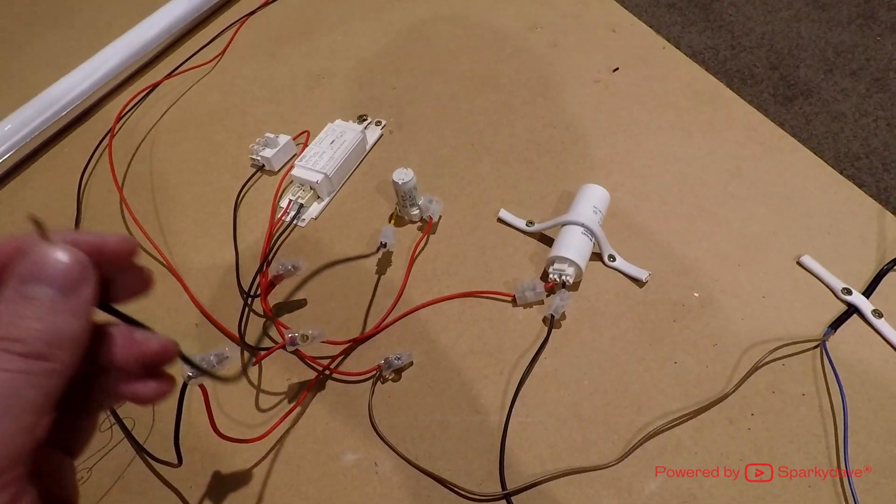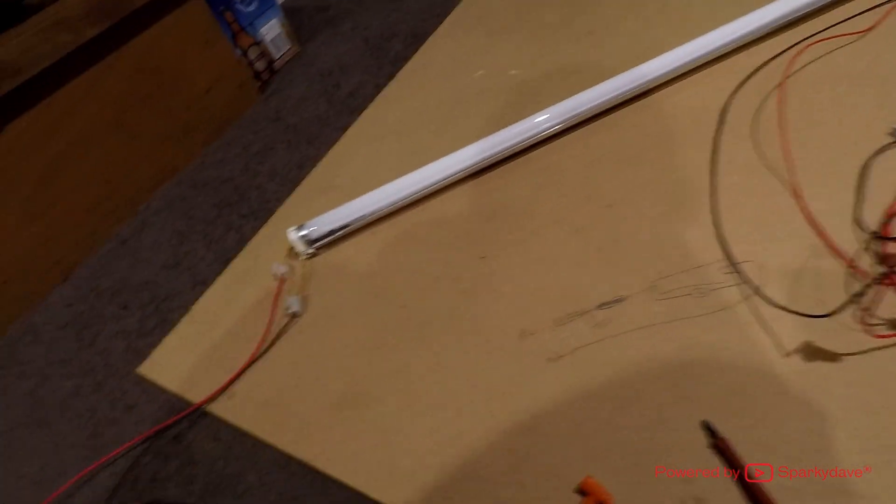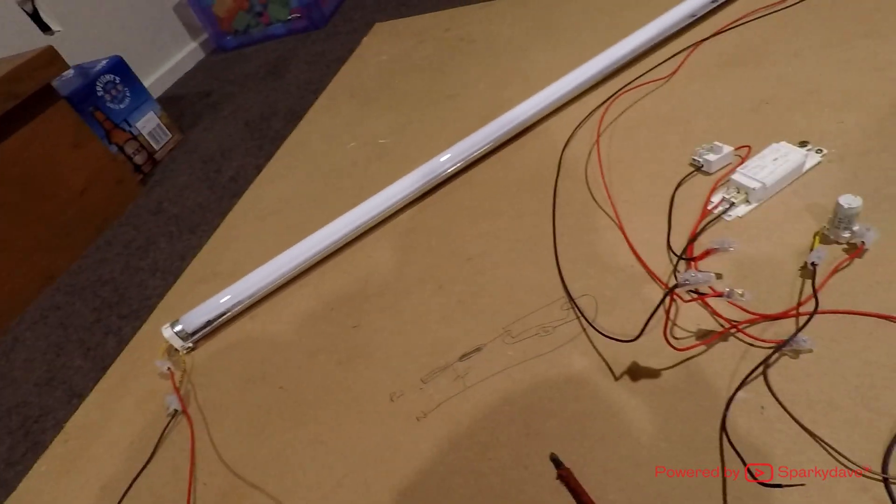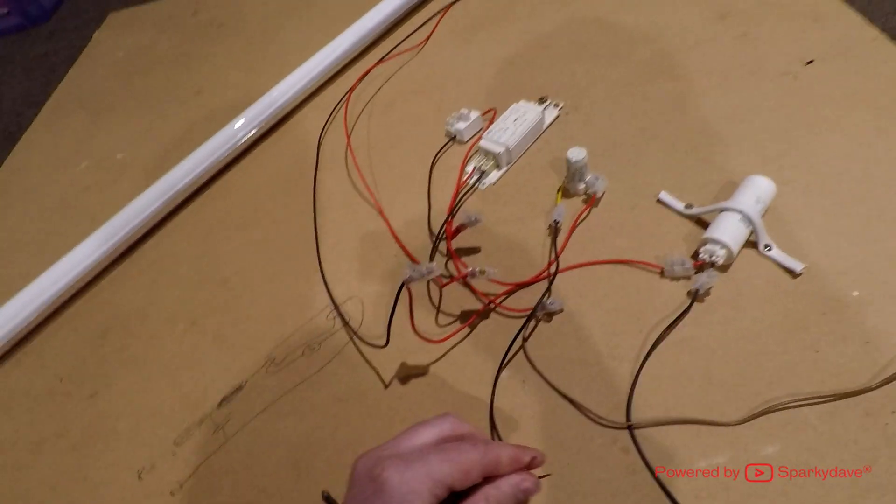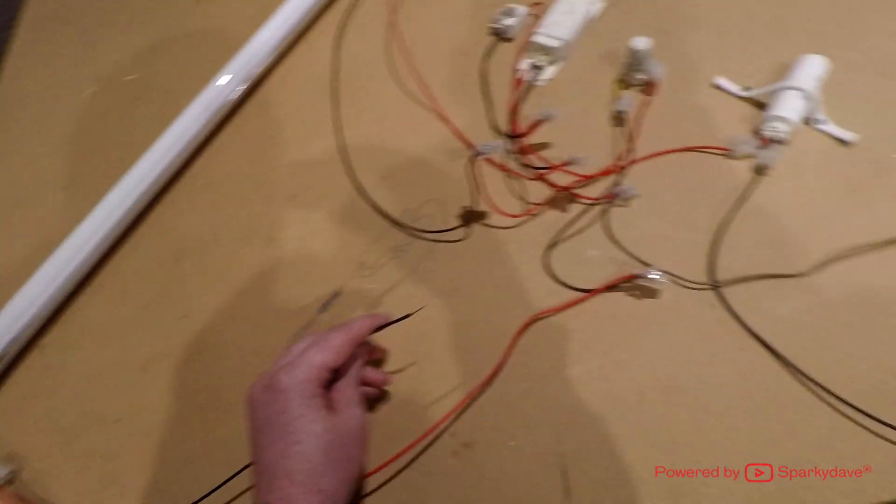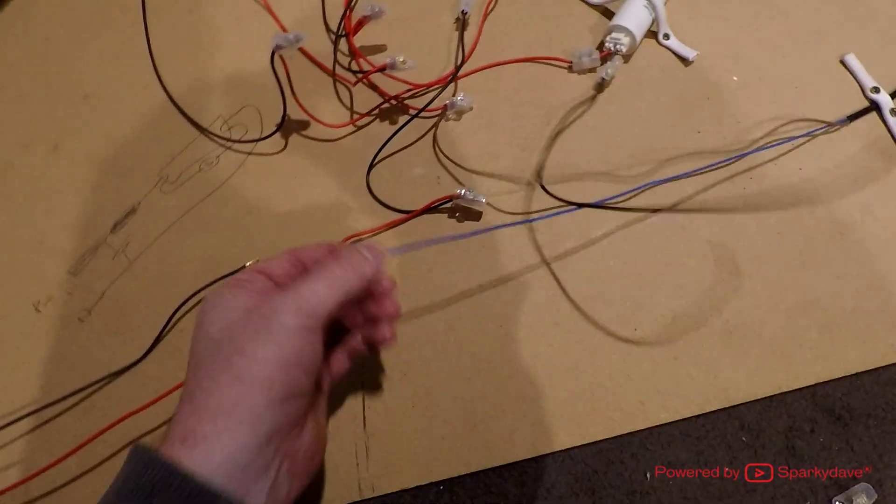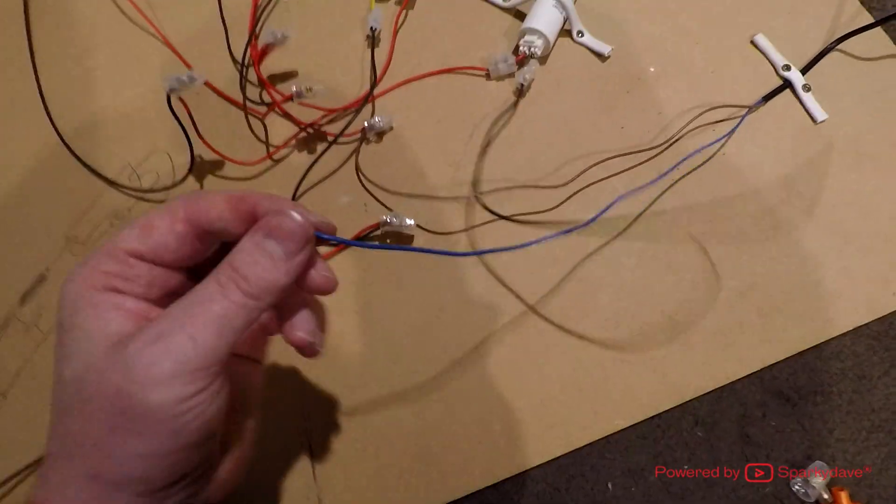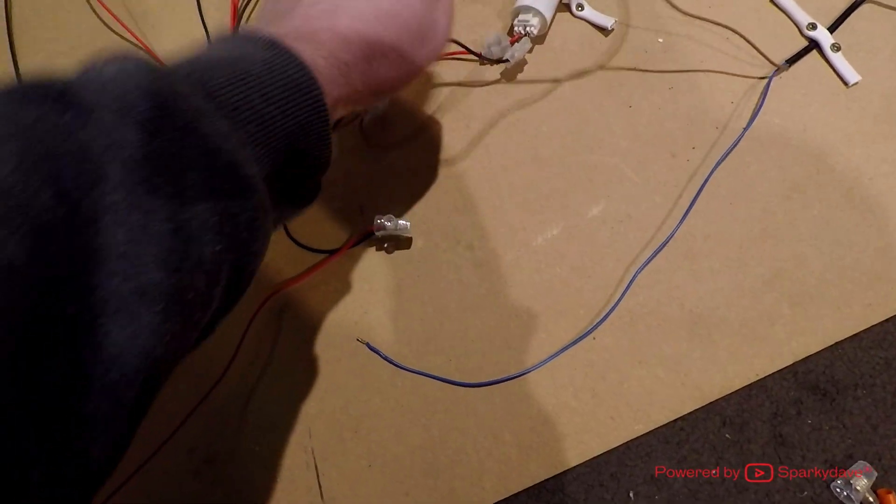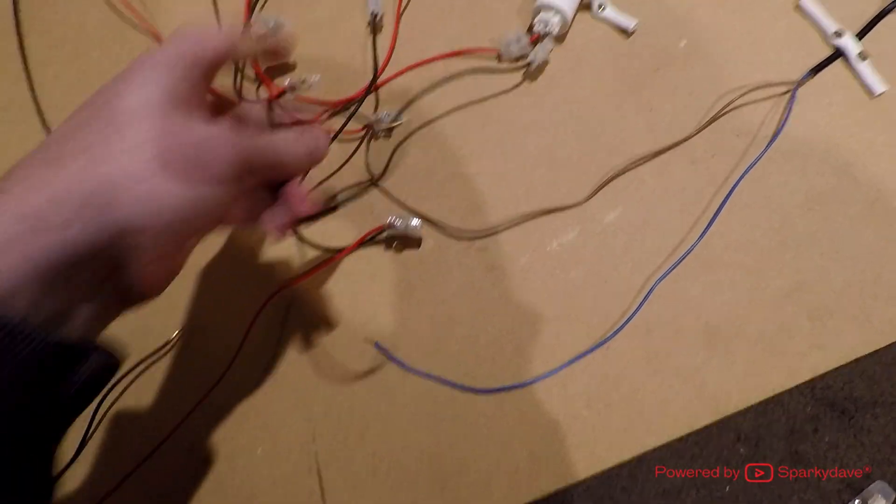From the black side of the starter I'm going to connect that to the opposite side red of the light fitting itself, and then the black side of the light fitting from that same end I'm going to tie in with the blue neutral cable and also the black tail from the capacitor.